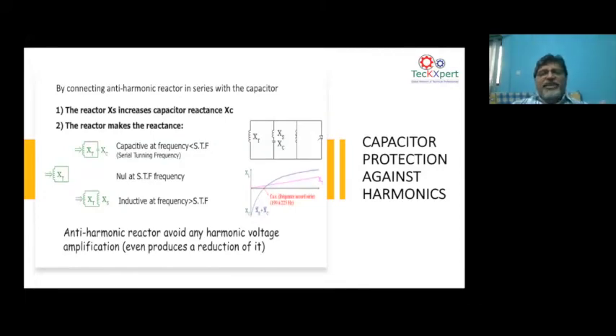So what do we do? The best option is to put a detuned reactor. That is what everybody does when it comes to a capacitor bank. You put a detuned reactor and tune the frequency away from the resonant point. That is what it shows. By putting a detuned reactor, you are trying to avoid the capacitor causing a parallel resonance because you have shifted the resonant point. For example, if you put the resonant frequency at 4.5 or 4.6, it's a non-integer number. So you will not have a VFD producing harmonics of 4.5 order or 4th order. It will only produce a 5th or 7th. So putting a detuned reactor is a way to shift the resonant frequency of the network.